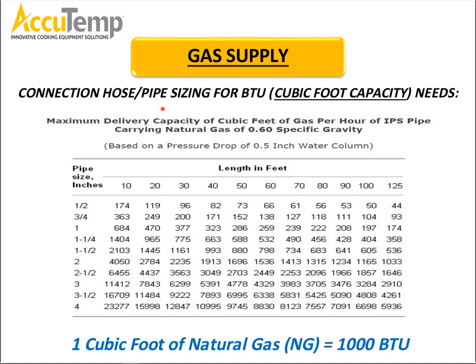Now, this is a little chart that I copied from the web. Here we've got pipe diameter and pipe length. Looking at this chart, we're going to use the 1-inch pipe diameter for example. Now this is for natural gas. That 1-inch pipe at 10 feet can support 684,000 BTUs. At 20 feet, that same pipe can support 470,000 BTUs. And at 30 feet, you see it dropping to 377,000 BTUs. A little FYI, remember 377,000 BTUs because we will be going back to it in a couple slides.